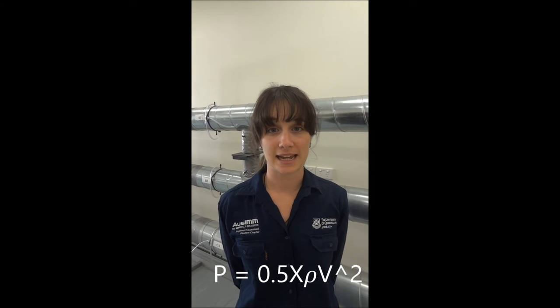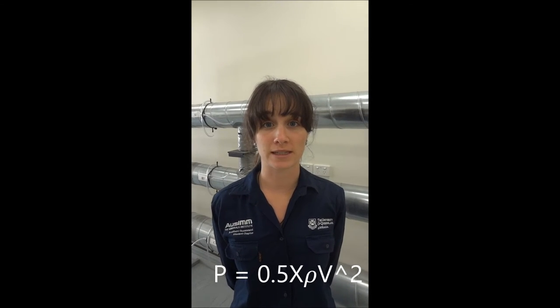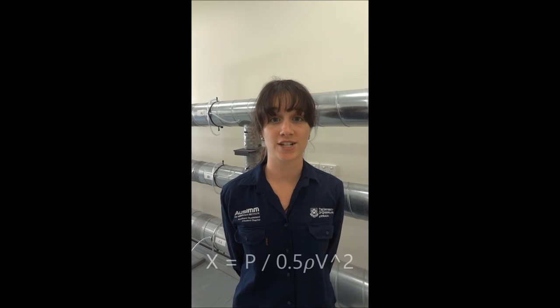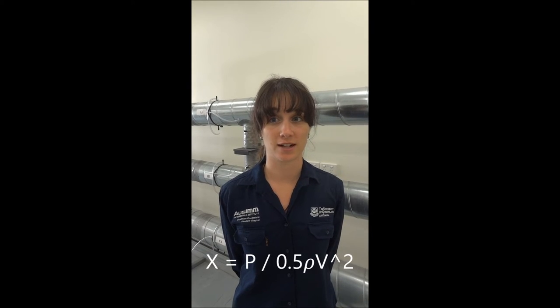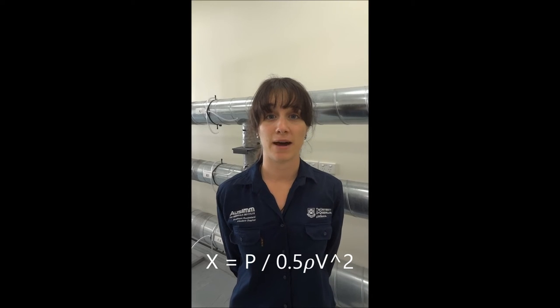The final section of the prac calculates shock losses through the bends and T-intersections of the duct through the formula displayed. Shock losses are losses caused by changes in the path of travel for the air, including bends, intersections, and changes in area of the duct. The shock loss factor x can be found by dividing the total static pressure by the velocity pressure.